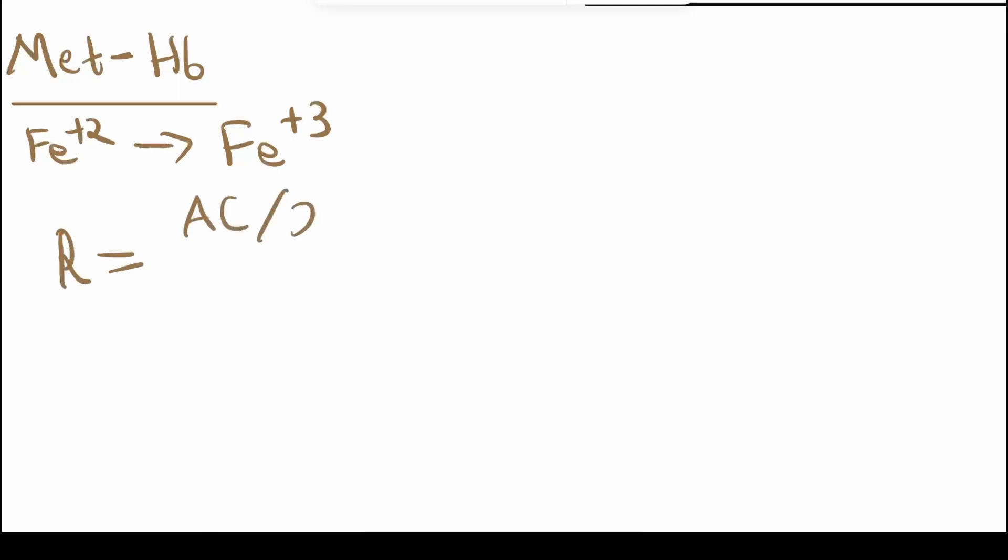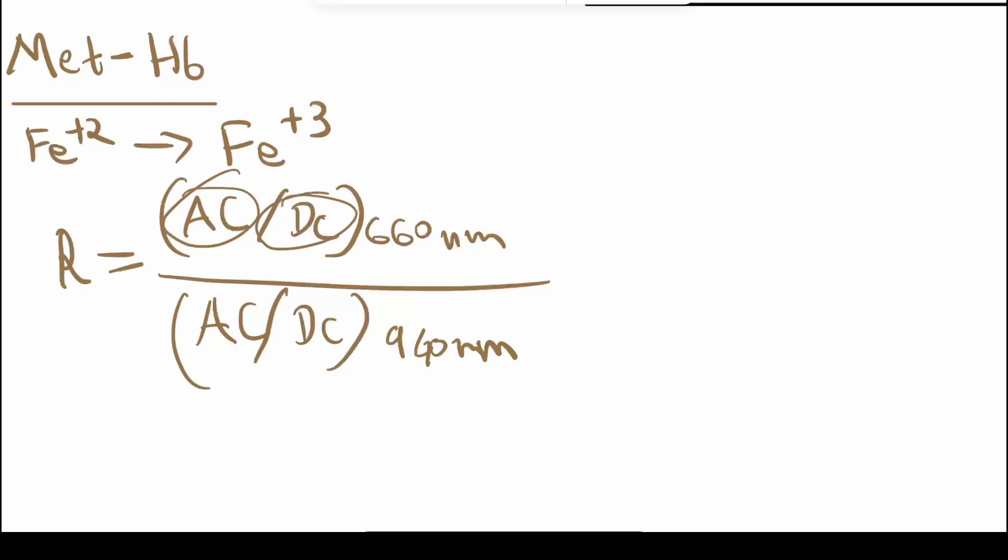The R number is AC/DC of 660 nanometers over AC/DC of 940 nanometers. What this is, is the ratio of active pulsatile flow over the non-pulsatile flow at 660 nanometers divided by the ratio of active pulsatile flow over inactive non-pulsatile flow observed at 940 nanometers. So this is reported as a ratio.